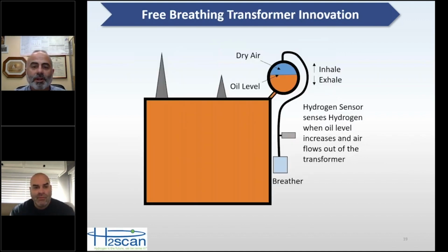And so I noticed here that I'm running out of time, so I'm going to go through the next slides very quickly. Some of the innovations I've seen is on a free breathing transformer. Typically, this is outside of North America, where you have the oil level going up into a conservator tank, and you have air above there, and it's free breathing because as the temperature goes up and down and the oil level goes up and down, you're breathing through a tube, through a breather, which is a desiccant system to keep that air dry.